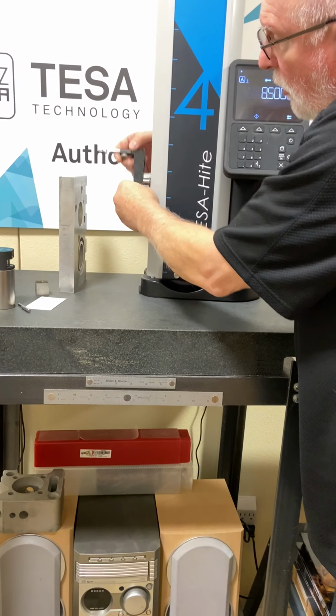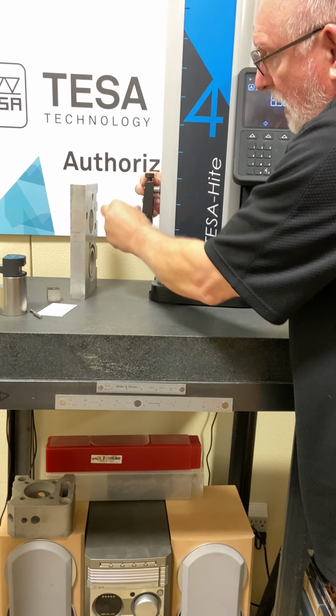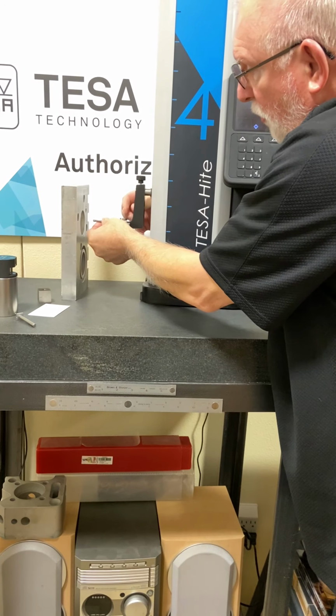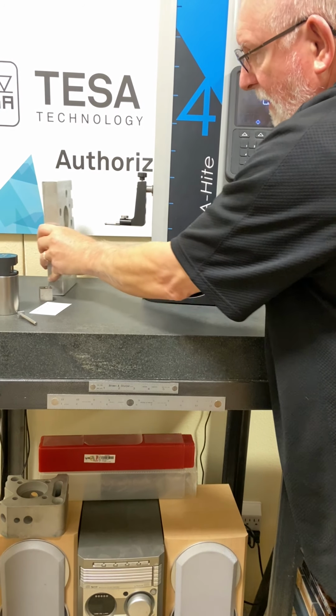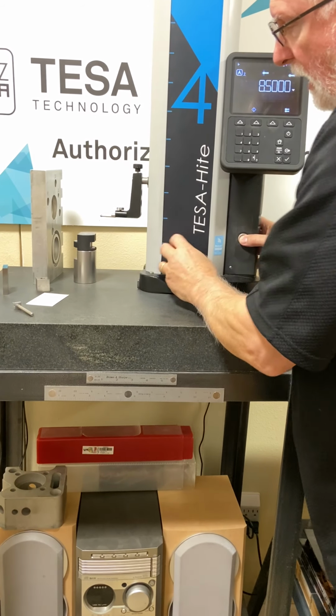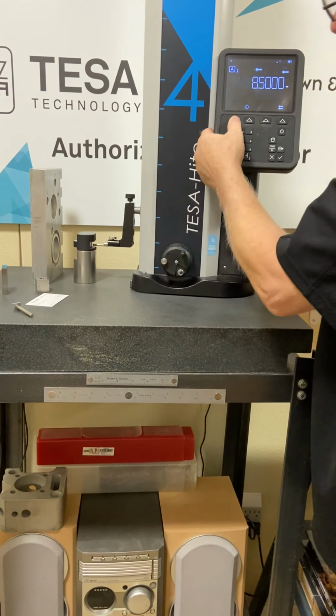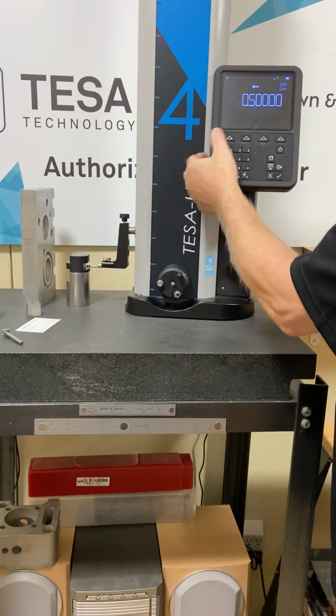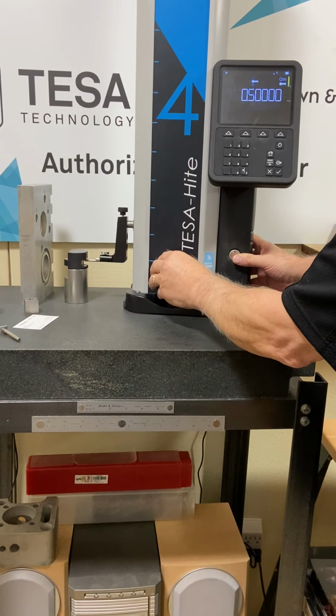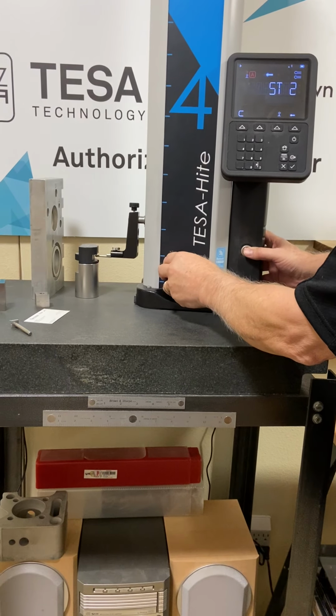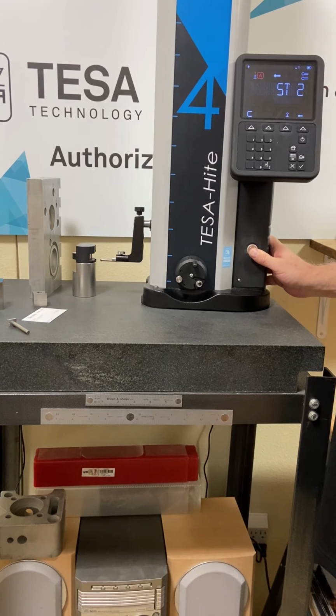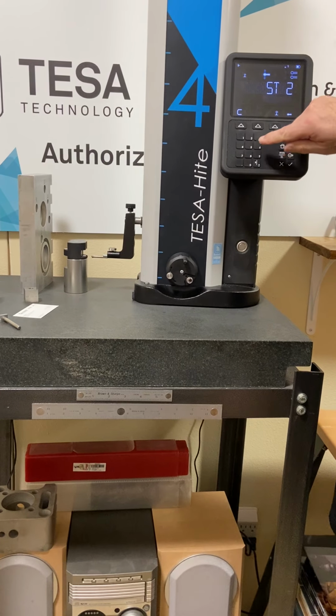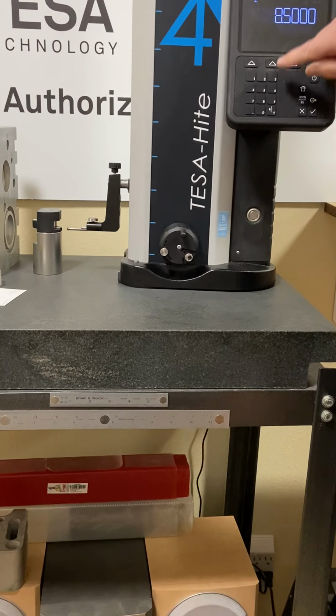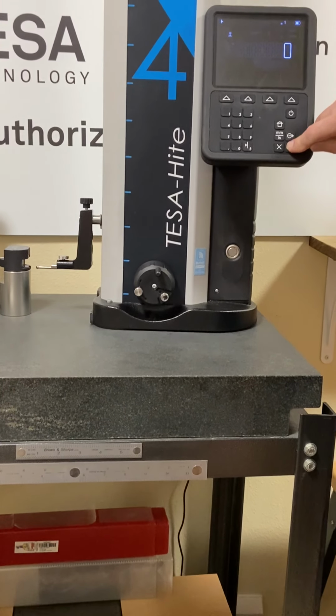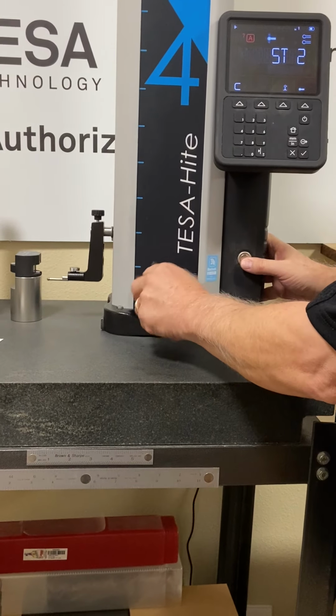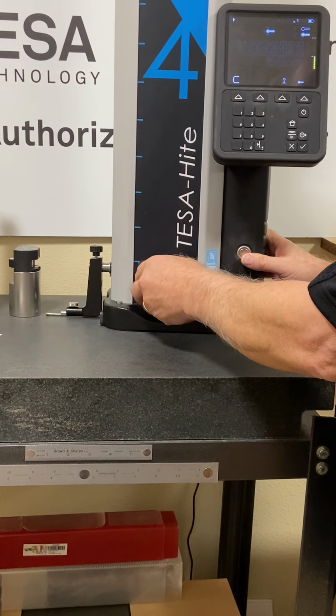The next procedure I'm going to go over is parallelism. To do parallelism, I'm going to put on the standard probe again. Again, I got to go through and calibrate it. So now I'm calibrated. Now that offset I put in at 8.5 inches is still in there, so I have to actually cancel that out. I'm going to go over here. I'm going to hit 0. I have to hit my enter key again. So now I can go down and establish the surface plate as my reference point again.